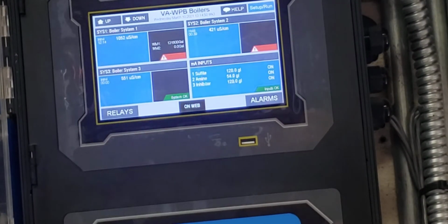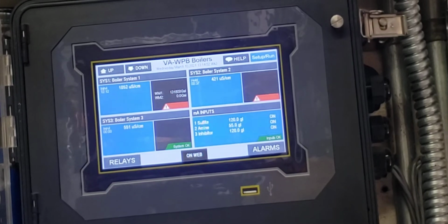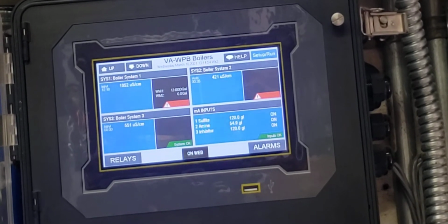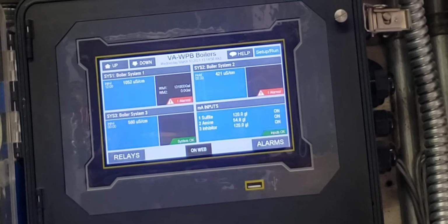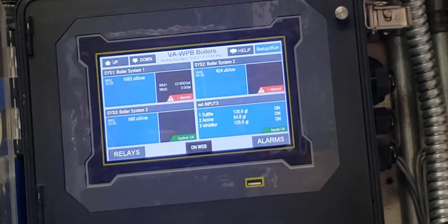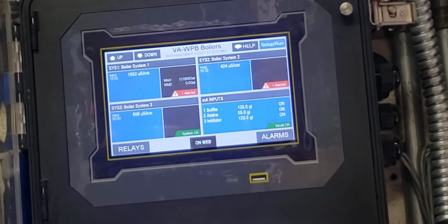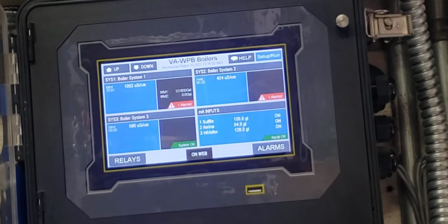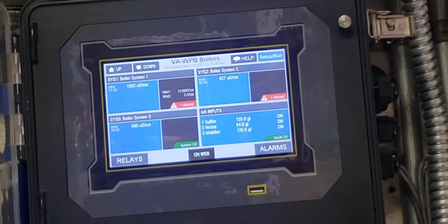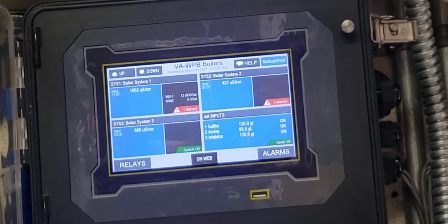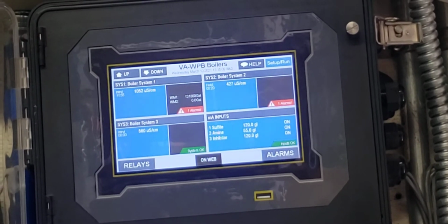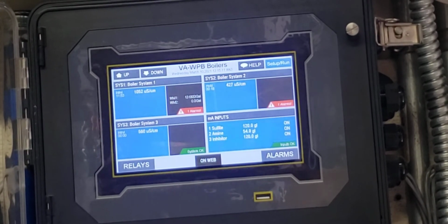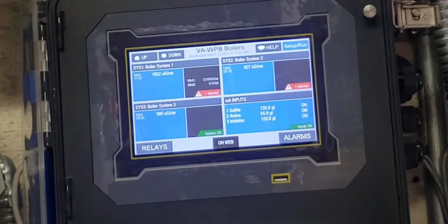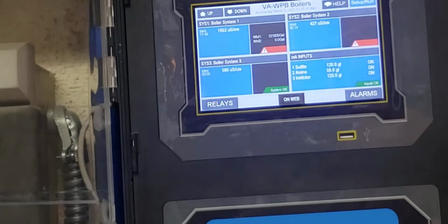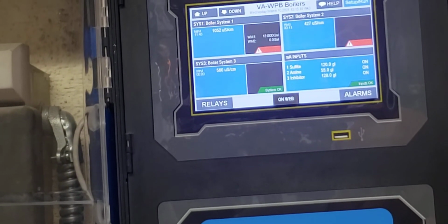So now it jumped up a little bit to 551. And again, we want to keep it as close as possible. If we get a huge differential, that's where we need to be really concerned. But I want you guys to be able to do those calibrations to really help fine tune it. The more we calibrate it, the more accurate we get it, and the easier it should run. We don't have to do that as much as the system starts to age.